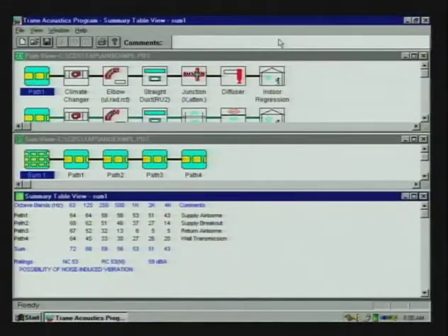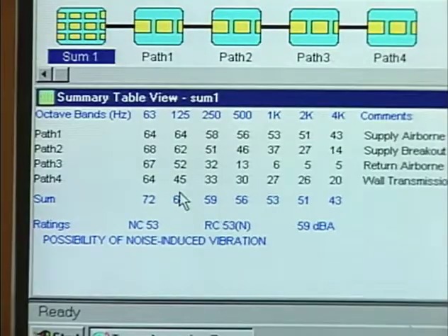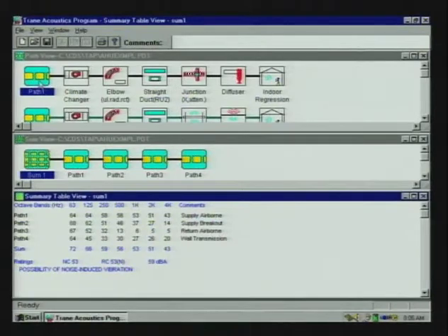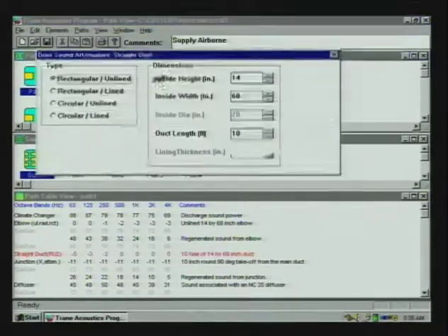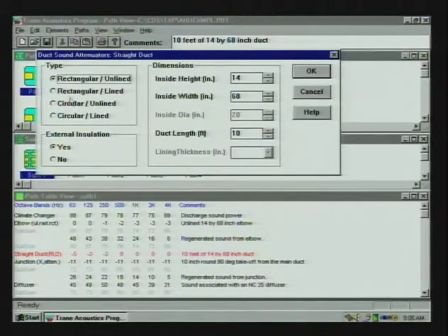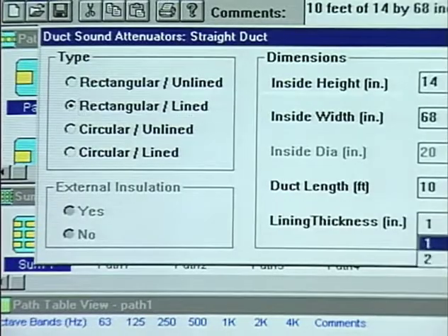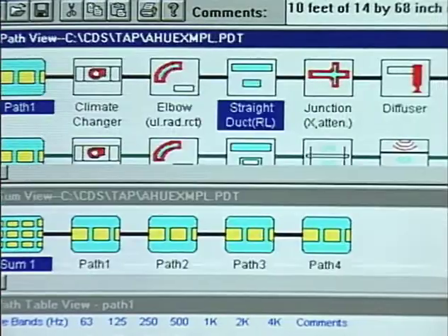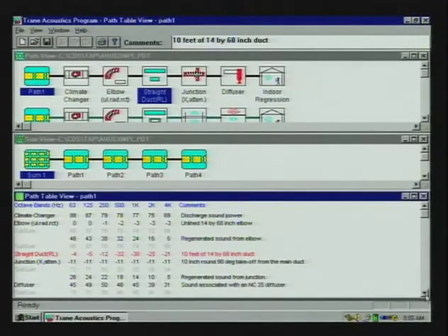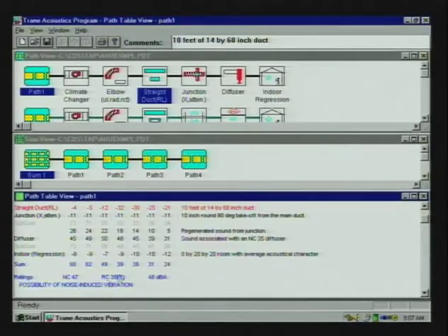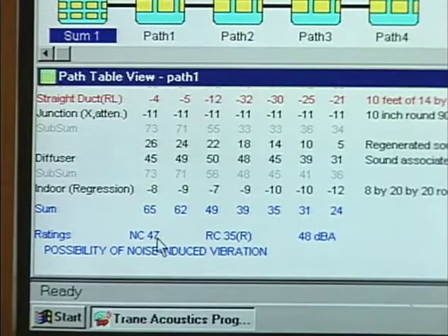At that point, then, I have the information I need to go back and look and see which of the paths are dominant. In this case, it turns out that all the paths are players here, at least in the first octave band. But to give you an example of what I would do to lower a path, let's go back up to our path 1, and I'll just open that straight section of ductwork. It's unlined duct. I'm going to change it to lined duct and make it 2-inch lining. Click OK. And now when I go back to my table view, I can see the effect of that. It went from an NC 53 down to an NC 47.